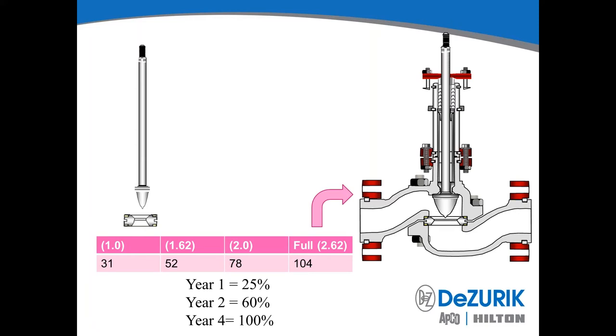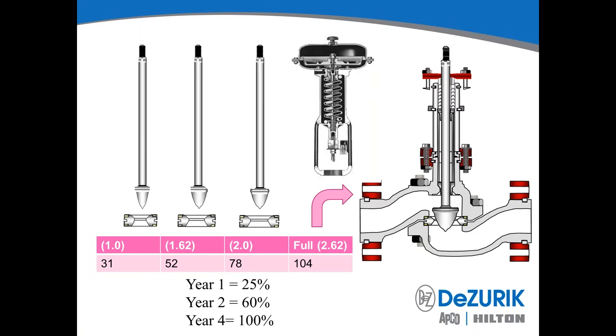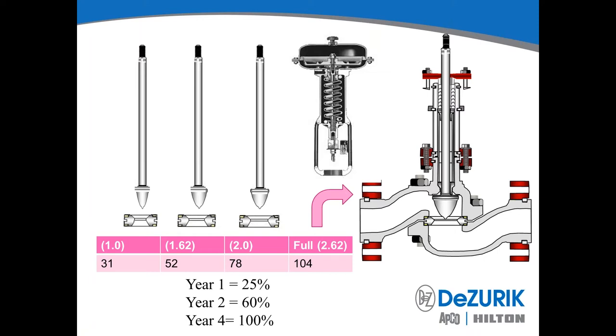Changing out the trims on a globe valve can be very labor-intensive and expensive. To get a CV of 31 for 25% capacity would have required a new valve seat and a new plug, and perhaps a new actuator because the stroke length changes on smaller trims. Then at year two you would have another trim set, and in year three another trim set. To change out the trims on this linear globe valve you have to undo the bonnet bolts, remove the actuator, change out your gaskets, and chances are you'll have to change your packing — particularly if it's graphite packing, as it probably would be in steam service. With my skills and experience, it takes about two and a half hours per valve to do all of that.